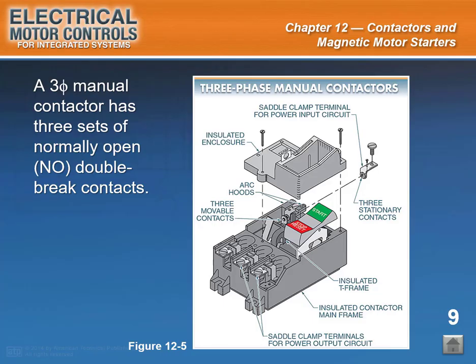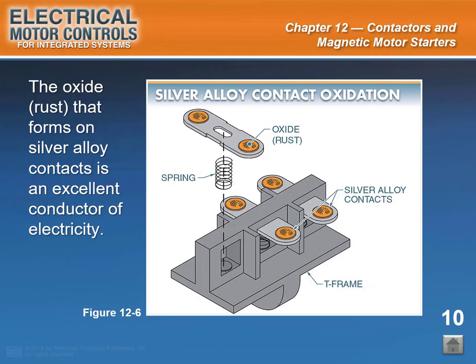One set of normally open double break contacts is used to open and close each phase in the circuit. The movable contacts are located on an insulated T-frame and are provided with springs to soften their impact. The T-frame is activated by a push-button mechanism. Similar to a disconnect, the mechanical linkage consistently and quickly makes or breaks the circuits. End of Slide 9. Start of Slide 10.